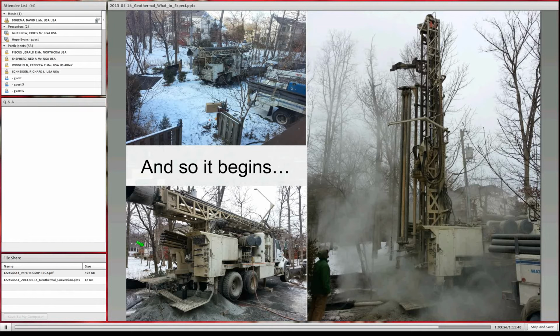We had a couple of questions about multi-use of the wells themselves. First, could you retrofit an existing water well to add a fourth pipe, or a couple extra pipes, for supply and return, turning it into a geothermal well? And could you add another pipe into the geothermal well to pre-treat your hot water and reduce the electrical load?